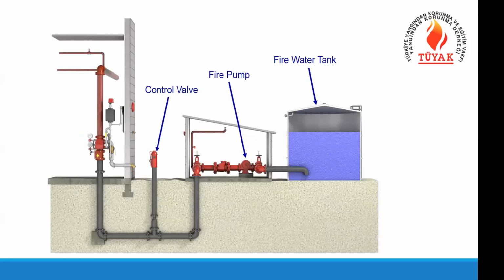especially in the projects in Turkey, almost in all projects, a fire water tank supplying our fire protection system. And there is a fire pump room. And inside the building, we have an alarm valve and sprinkler systems. So there is a complete system consisting of water supply, pump system, and the valve systems. And in the end, we have the sprinklers.